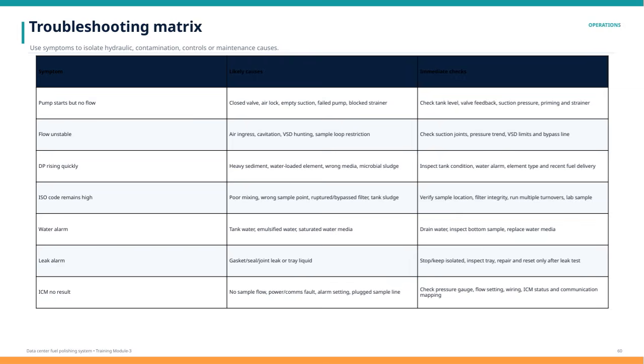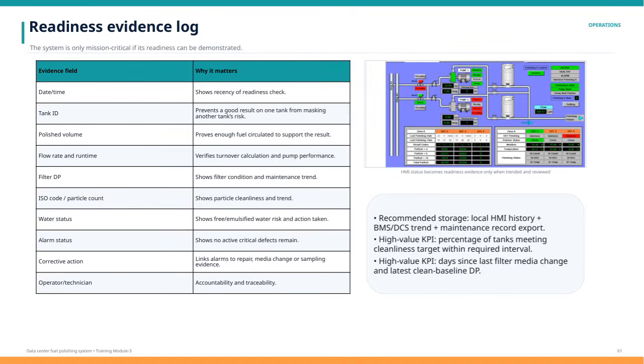Here we have the concept of a readiness evidence log, which is crucial for mission-critical systems. Essentially, a system is only considered mission-critical if we can actually prove its readiness. That's why tracking and documenting evidence is so important. Let's look at the core elements in the evidence log. The date and time show how recent the readiness check is, ensuring we're working with current information. The tank ID helps us avoid mixing data between tanks, so we don't overlook risks in any individual tank. Polished volume confirms that enough fuel was circulated to make the test meaningful.